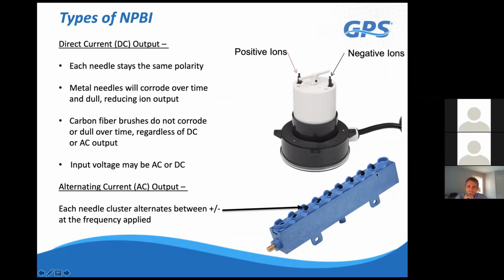The second type of technology we provide is the alternating current systems. So we have these modular bars, and these sections come in 6-inch sections, and they snap together for whatever size you need for the size air handling system that you have. So here we have a carbon fiber brush, and that brush alternates between plus or minus based on the polarity being applied and the frequency being applied. In North America, the frequency out of your standard outlet is 60 hertz. So 60 hertz equates to 60 times per second. This is alternating between plus or minus, and so it's static neutral.